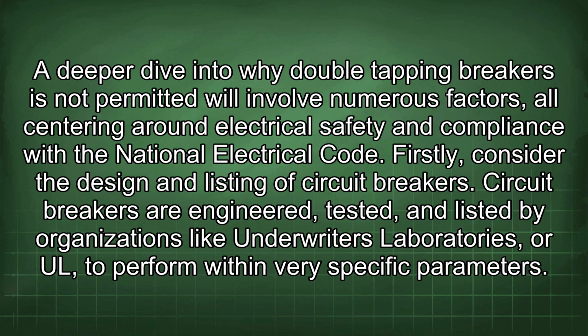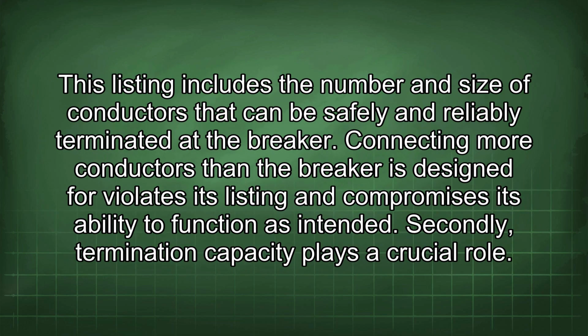Firstly, consider the design and listing of circuit breakers. Circuit breakers are engineered, tested, and listed by organizations like Underwriters Laboratories, or UL, to perform within very specific parameters. This listing includes the number and size of conductors that can be safely and reliably terminated at the breaker. Connecting more conductors than the breaker is designed for violates its listing and compromises its ability to function as intended.